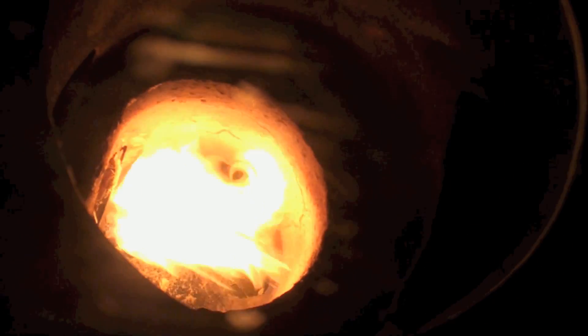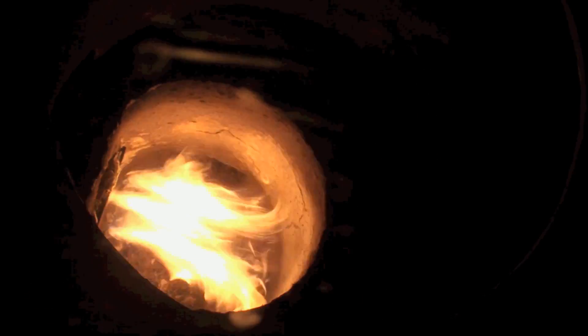Okay, top's off and fires in the combustion chamber. Now this flame has got an awful lot of air in it. You can see this is not a flame retention burner. I'll do it with a flame retention burner later.